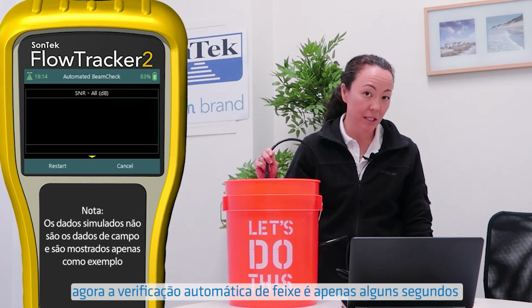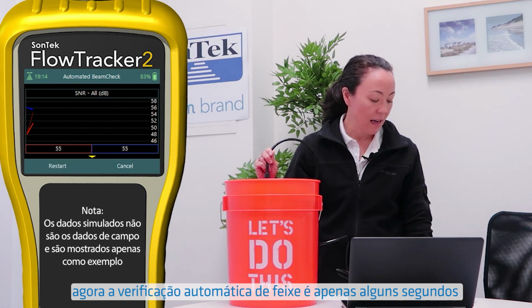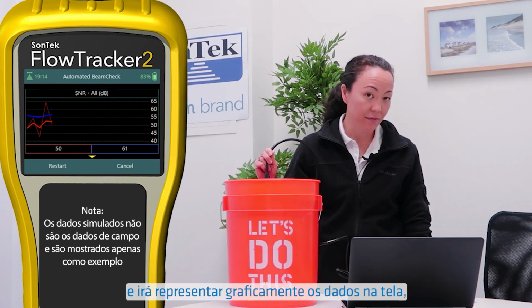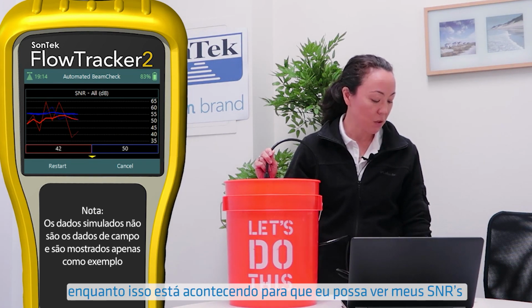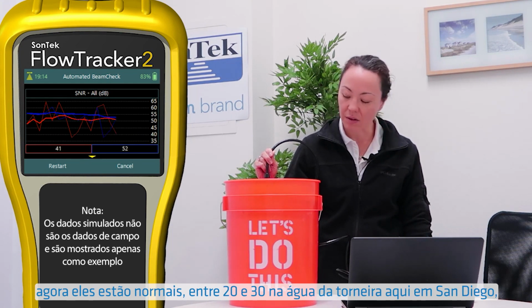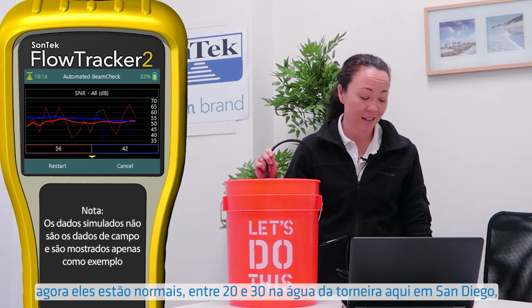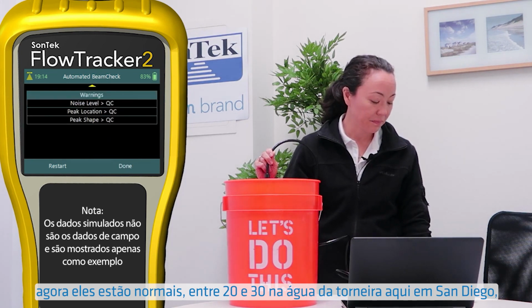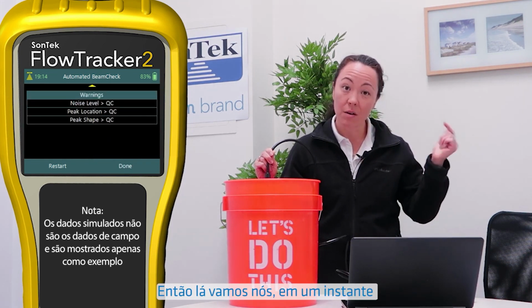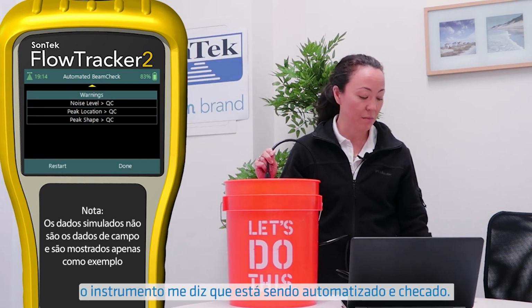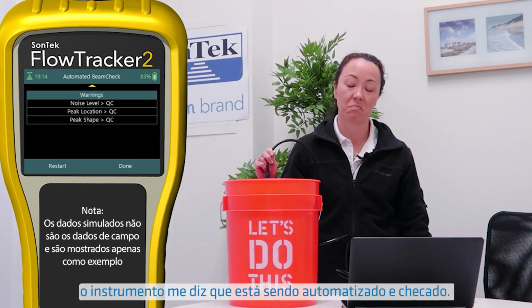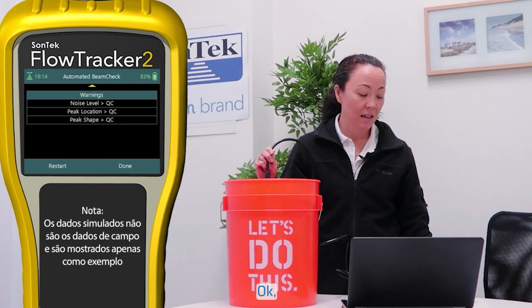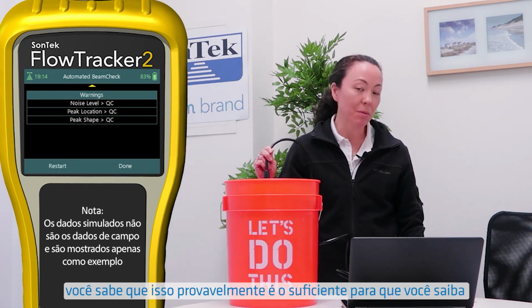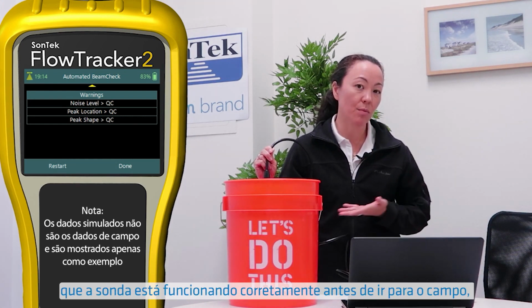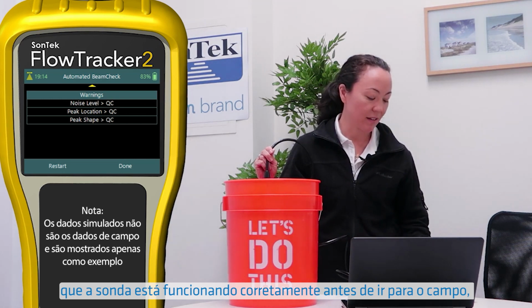Now the automated beam check is only a few seconds, and it will graph the data on the screen while it's happening, so I can see my SNRs. No, these are normal. They're between 20 and 30 in the tap water here in San Diego. And then there we go. In an instant, the instrument tells me automated beam check passed. Okay. You know, that probably is enough to go on to let you know the probe is working properly before you head to the field.